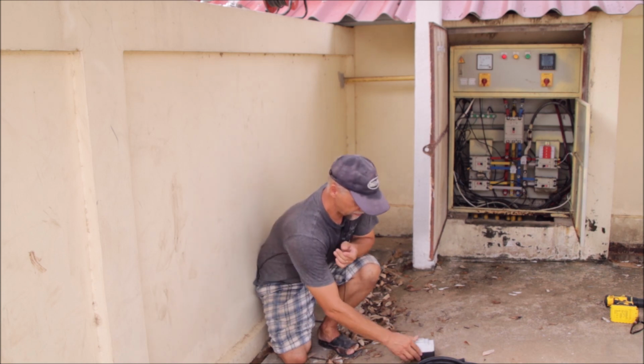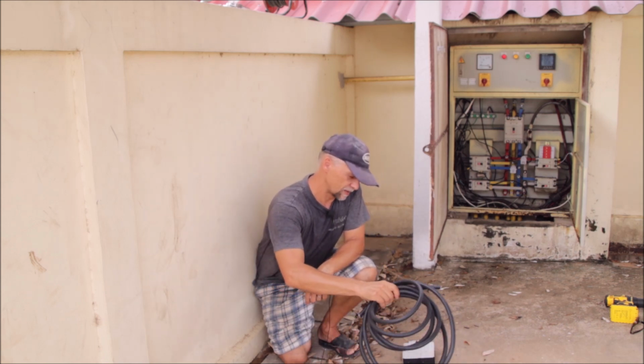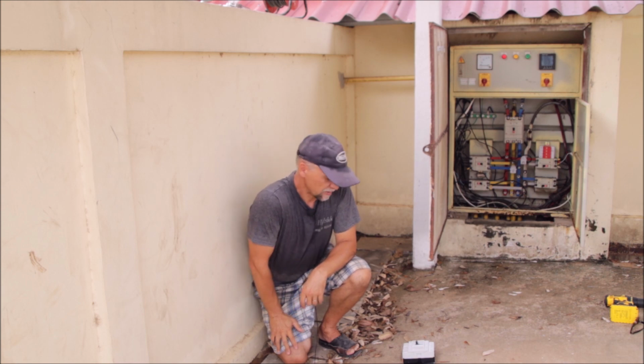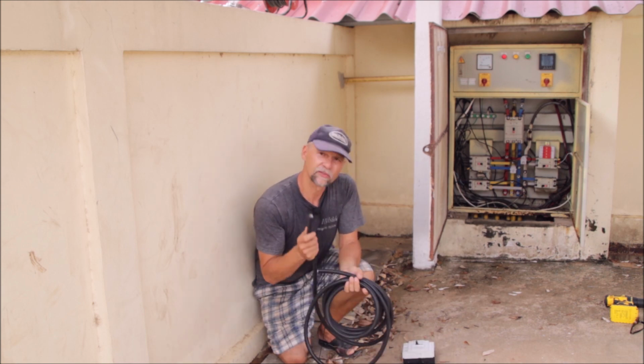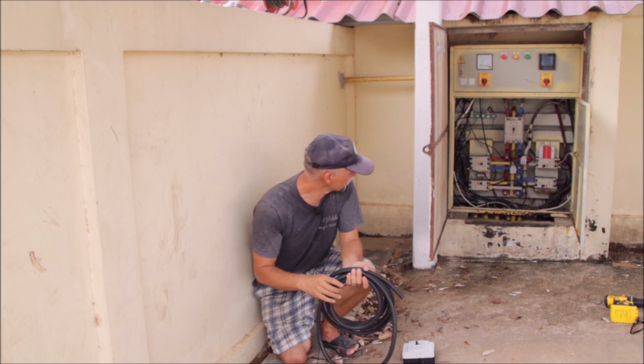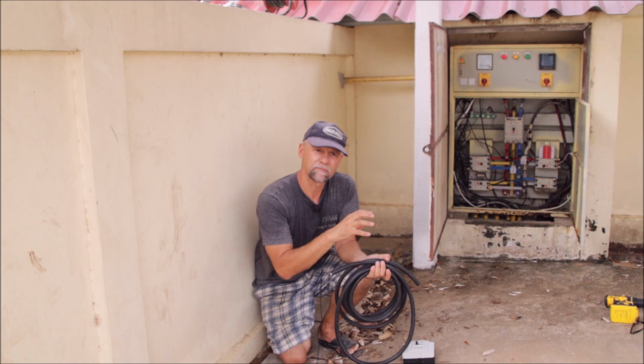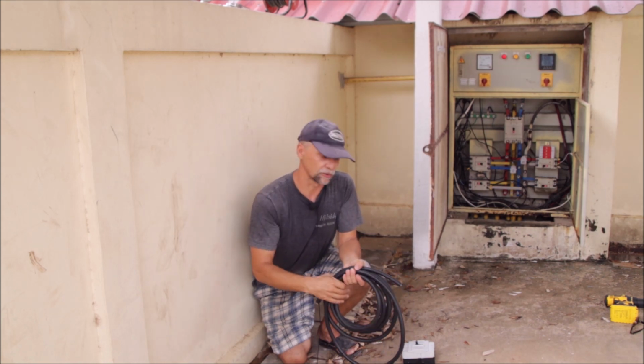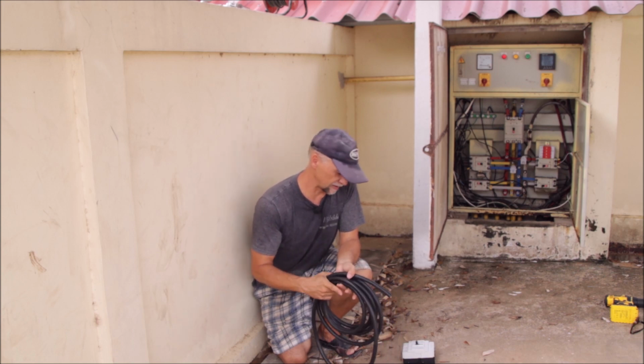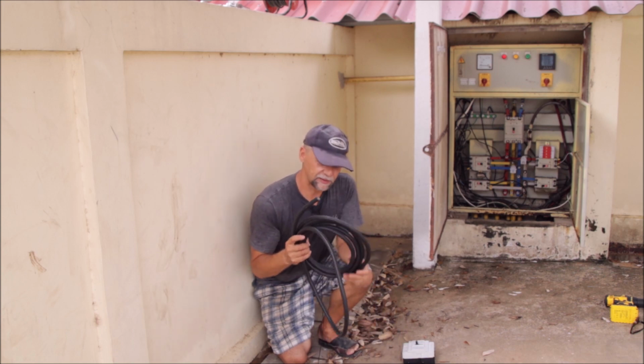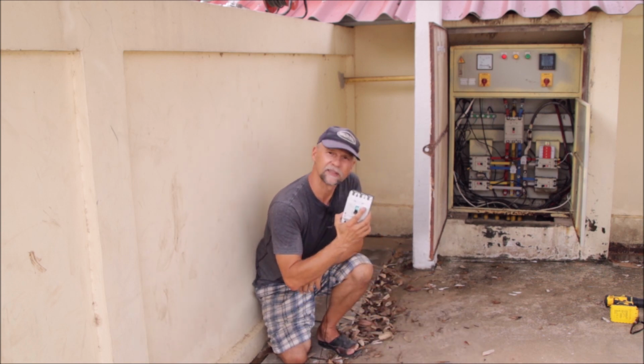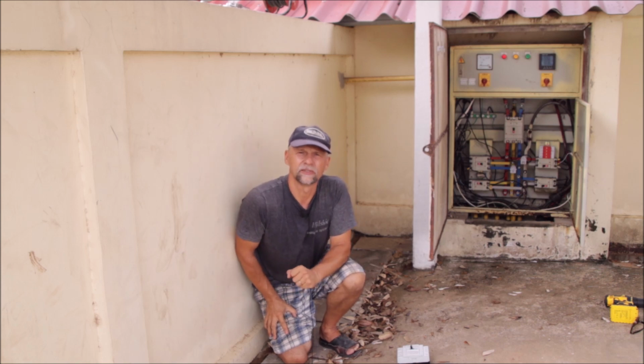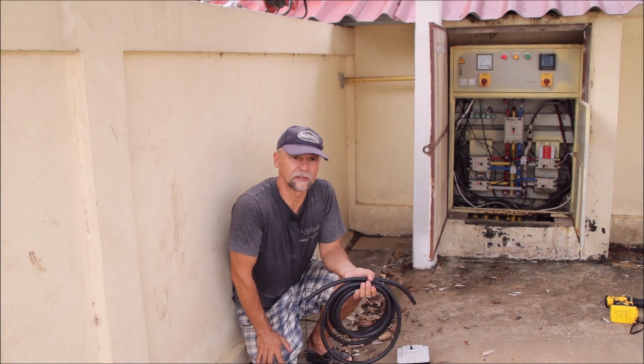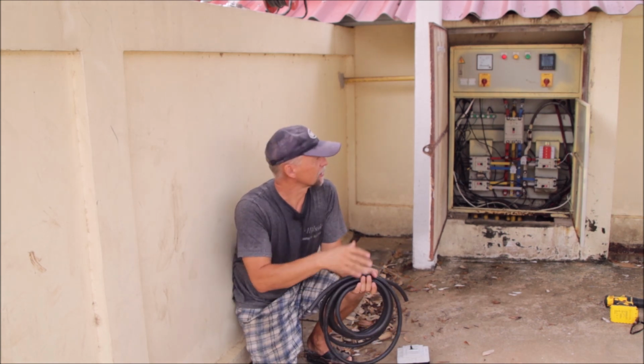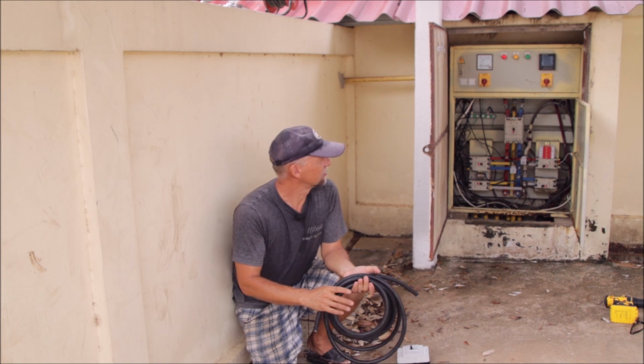So why is that? Probably you will think it has something to do with my charger here, because we are going to connect this 3-phase cable, this is a 6 square millimeter, to the same breaker as the 10 square millimeter, which goes to the main building. So the breaker will actually serve both of the lines. With 6 square millimeter, less diameter, I will probably need a lower amperage breaker, but this is not true. This cable here is 5 meters long. The next distribution point, the load center or wall box, is only around 4 to 5 meters away.